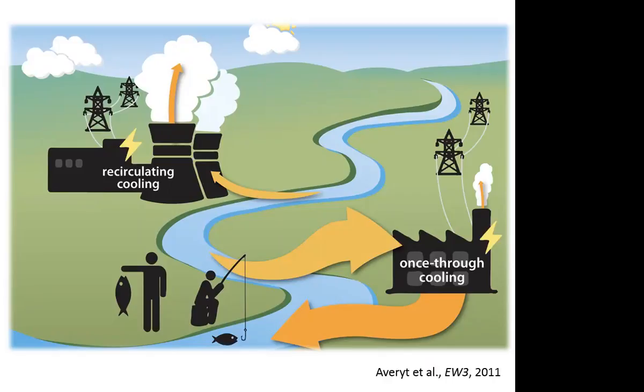The other trade-off with a once-through power plant - remember, you bring cold water in and spit out hot water - is that on average, the effluent temperature is 10 degrees Celsius, or 17 degrees Fahrenheit, hotter than when it came into the plant. So you can imagine there are significant issues relative to aquatic habitat and fisheries.